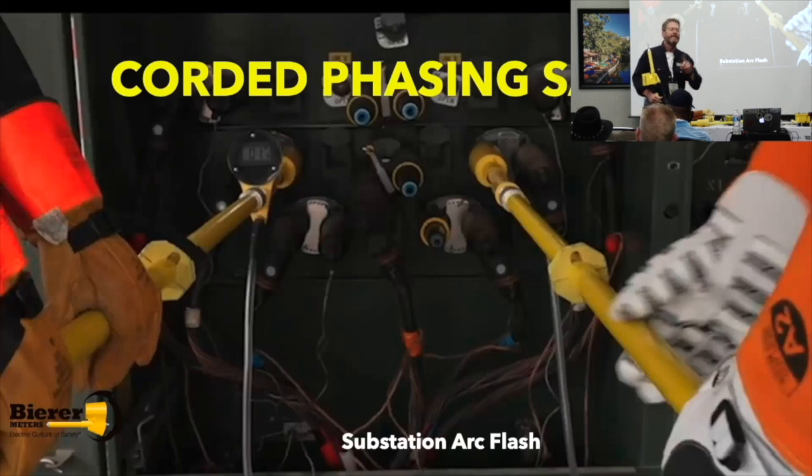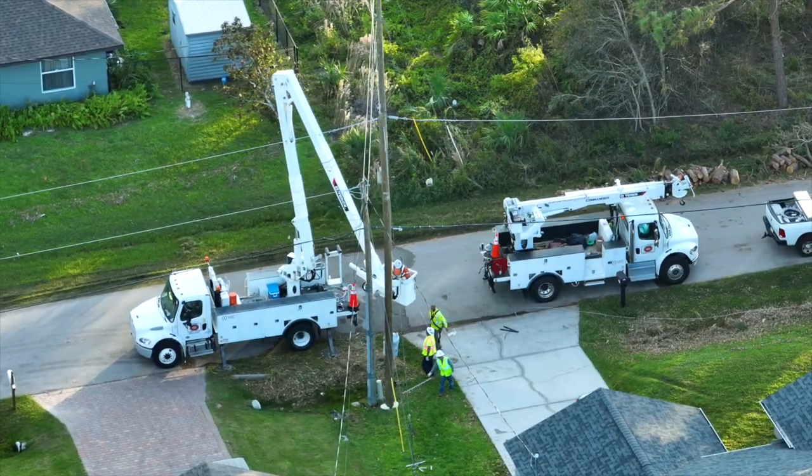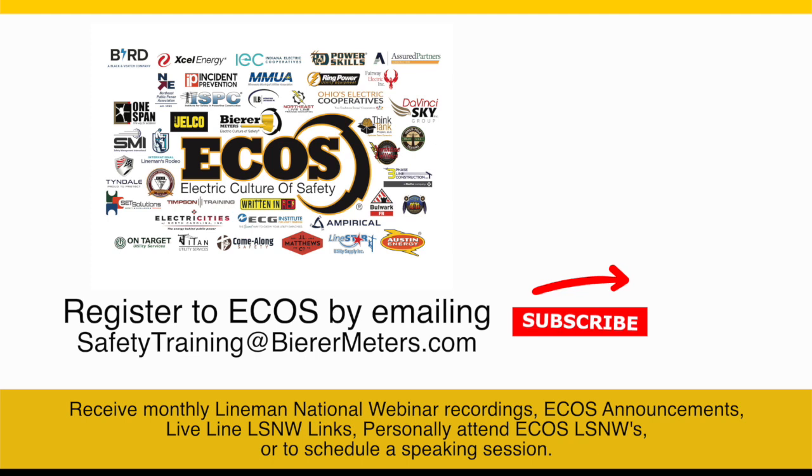What if, when they were doing that job, they were not training their linemen to be 36 inches away from the cord? What if that cord was next to the thigh? What if the cord was by his ankle? He would either lose both legs, one leg, or be dead — and maybe both of them. Stay away from your cords. I don't care if it's our tool or anybody's. Don't get close to your cord.